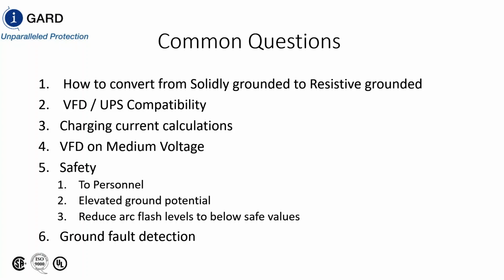Yes. Another question that we had was how does high resistance grounding reduce arc flash levels to below safe values? And you touched upon that. It doesn't. Employing a resistance grounded system does not lower incident energy. It only reduces the probability or the risk of having a fault propagate to a phase-to-phase or three-phase fault. As you said, all the other mitigation techniques that you use, the maintenance switch, differential protection, zone selective interlocking, they only come into effect after the fault occurs. Resistance grounded system is really the only thing that comes in that helps you before the fault occurs. So it's like an early warning system.